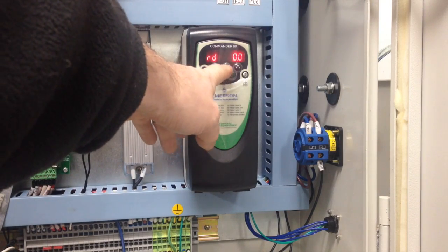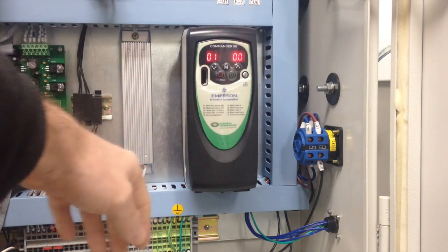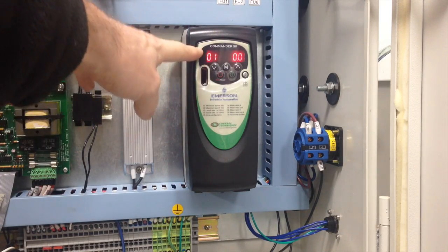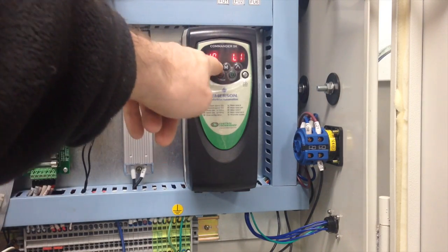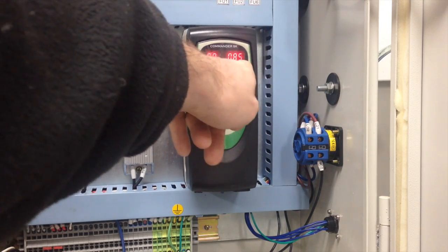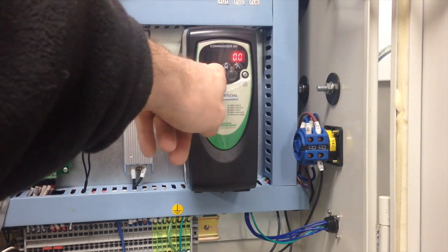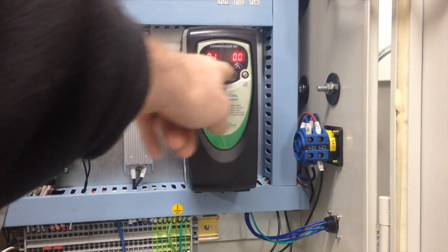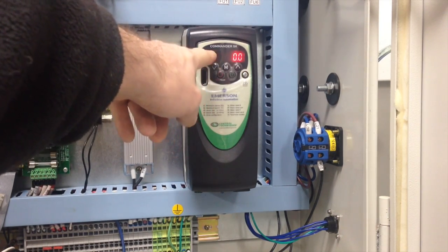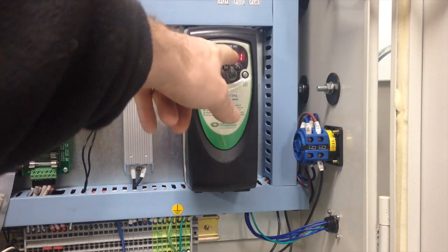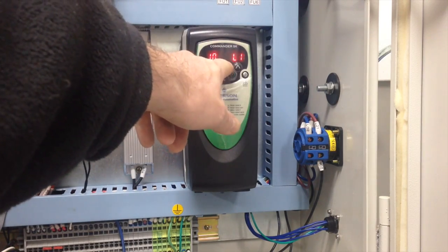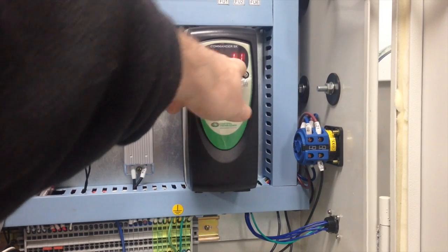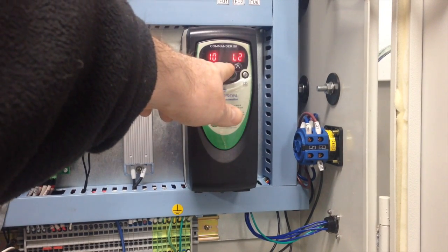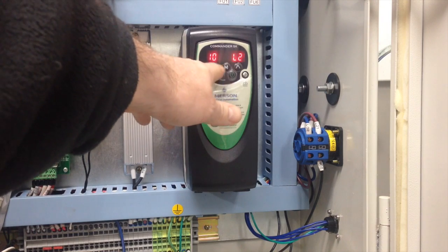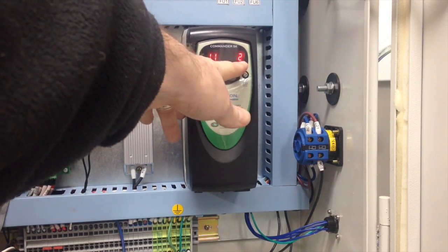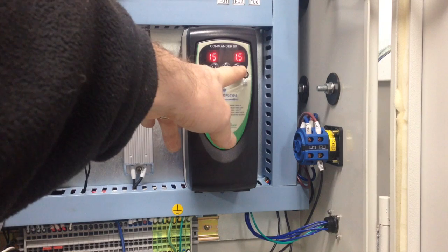If we hit the M button once, we get into sort of lists of parameters to view them, and then just scroll down. And if 10 is the maximum that you can get to before it jumps back to 1 again, then you know that you're only at the first level access. So go to parameter 10, and you'll see L1 written here. Press the M button again, change that to L2, and then hit M button again. And now we can go further than number 10.